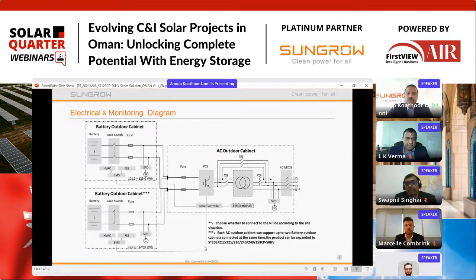So the electrical and monitoring diagrams, this is a schematic diagram for the solution. When we're talking about the solution for SunGrow C&I BESS systems, we have an AC outdoor cabinet and battery outdoor cabinet. One AC outdoor cabinet, 50 kilowatt PCS, can be connected to a maximum of 2 battery banks. Each battery bank is rated from 101 to 129 kilowatt hour, so the maximum size with the 50 kilowatt is 258.